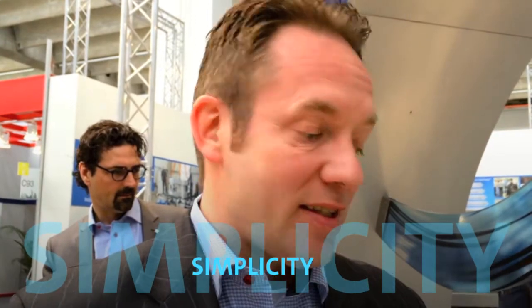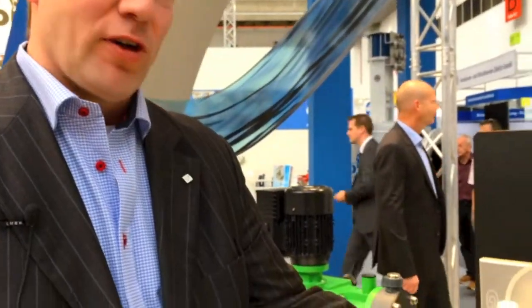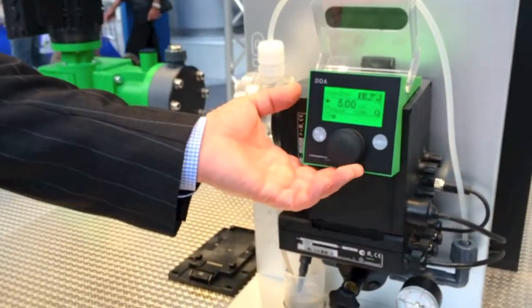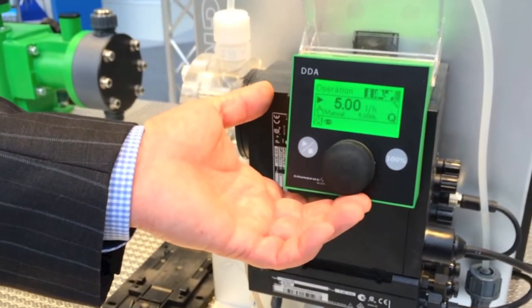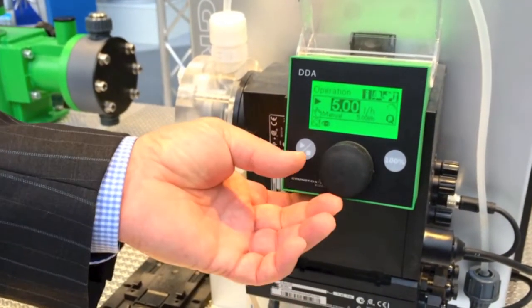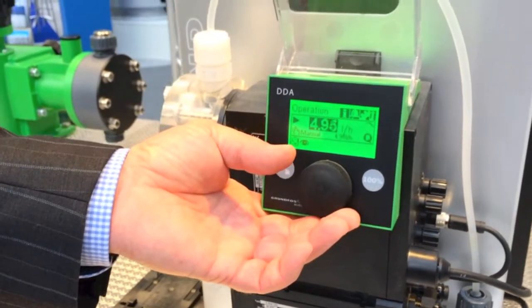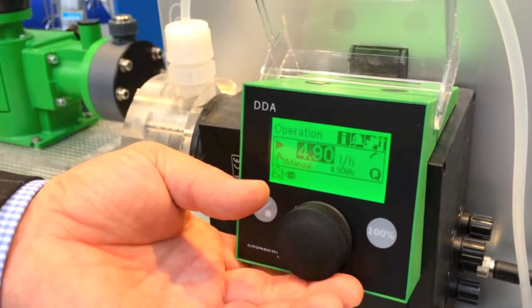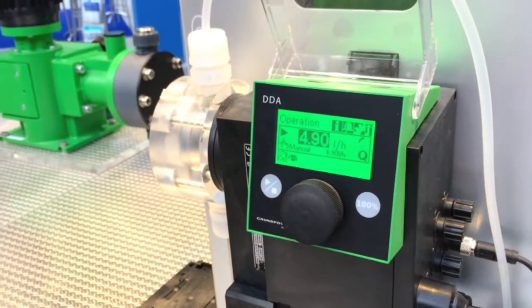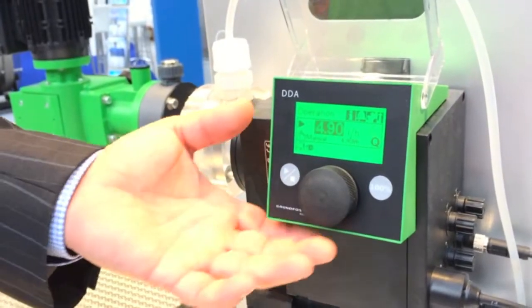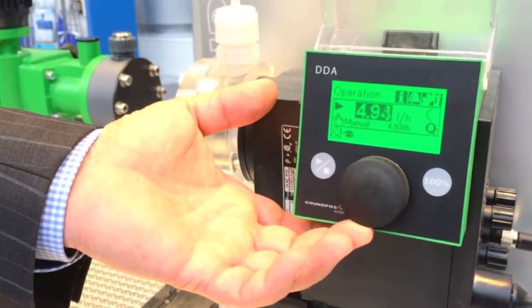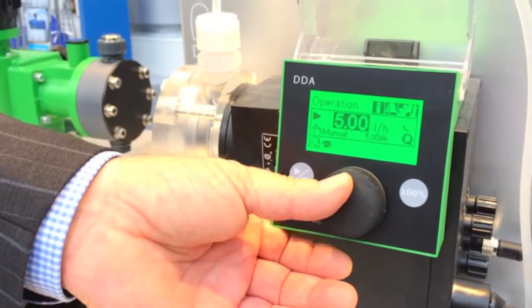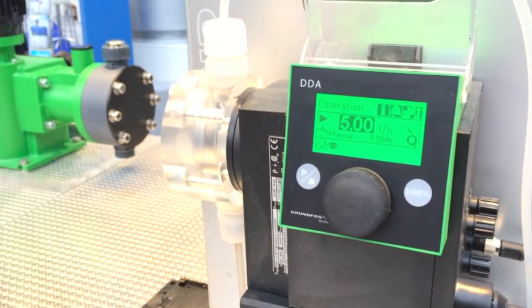The other point is the simplicity of how to operate a pump. With the Smart Digital, you can select the needed flow directly with our push and turn button. It's very easy to operate. You go to the field where you want to select the flow, and then you can directly set the flow that you need. You don't need any graphs or correction factors to adjust the stroke length. If you want 5 liters per hour, you select 5 liters per hour, push the button, and then the pump will deliver 5 liters per hour.